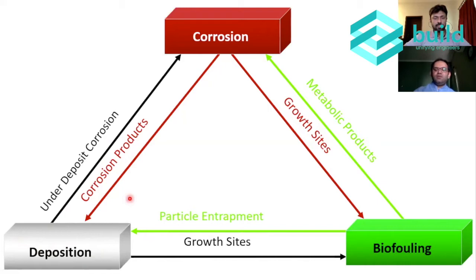On the other hand, if we use very high purity water for cooling and eliminate deposition but don't focus on corrosion, corrosion will start, because water is corrosive in any form, and when there are fewer salts in water it becomes more corrosive. So not focusing on corrosion will ultimately create corrosion, and corrosion products will lead to deposition. Similarly, if we don't focus on biofouling - bacterial growth in the system - it could also lead to corrosion and deposition.